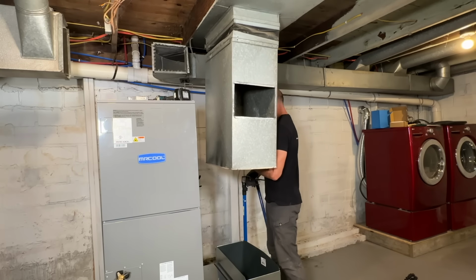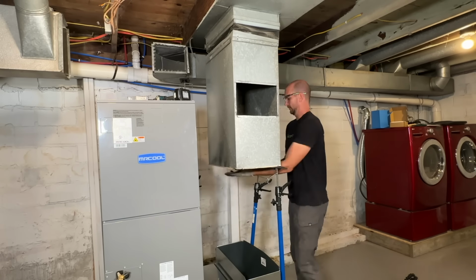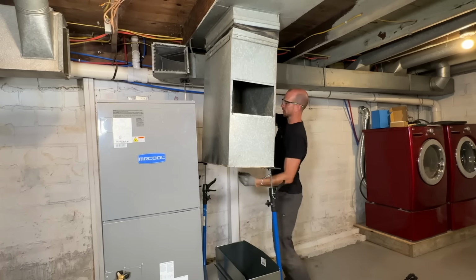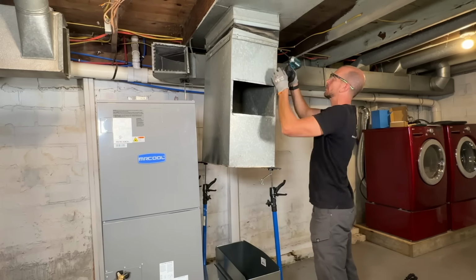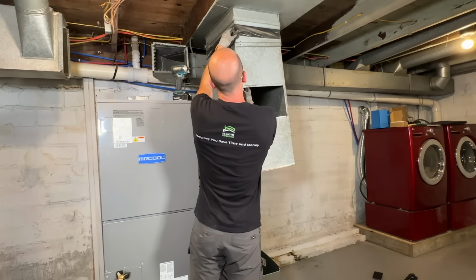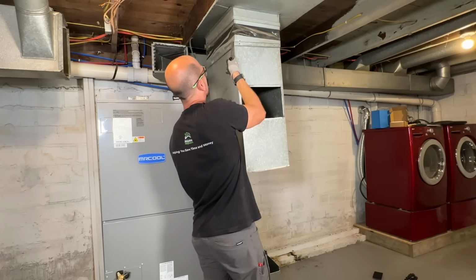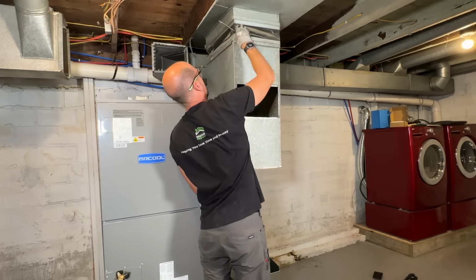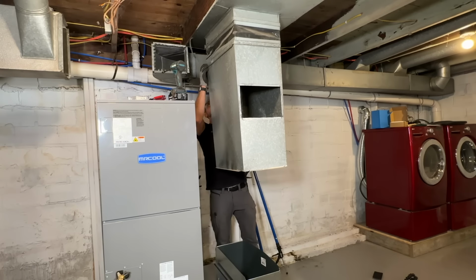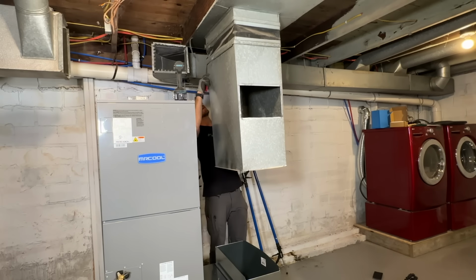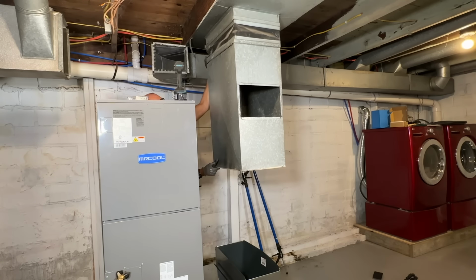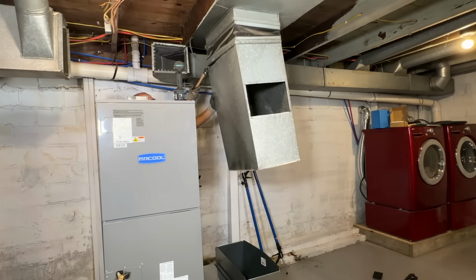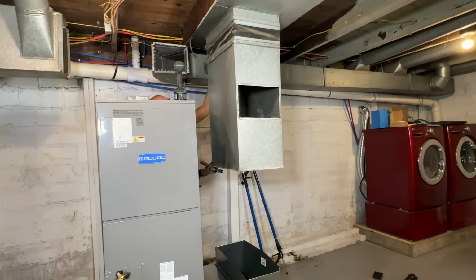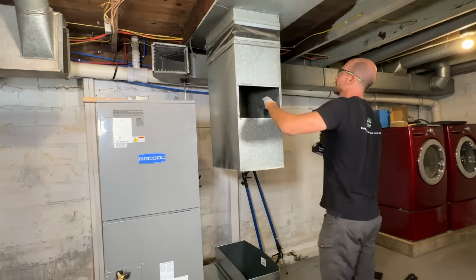And then whenever possible, use the ductwork that you removed. So this is the section of the cold air return that I removed from the old oil burning furnace. Now I just had those temporary stands so I could sink a few sheet metal screws, and now I'm lining up each of the 4 different S channels. Once I get those lined up, top and bottom, then I can go ahead and just sink a couple sheet metal screws in each side and everything will be secure.